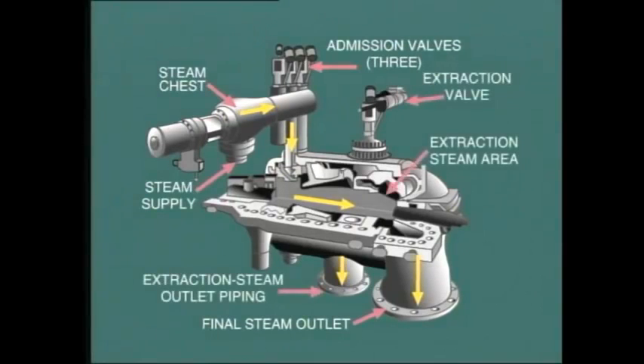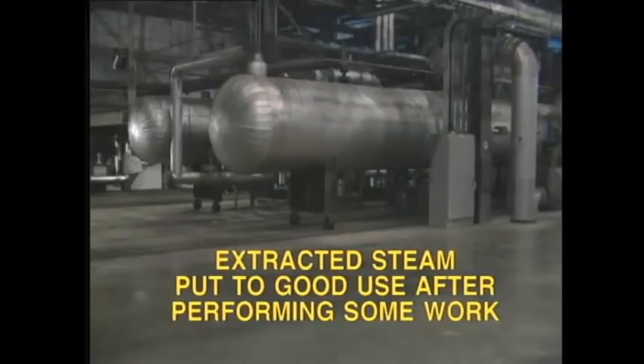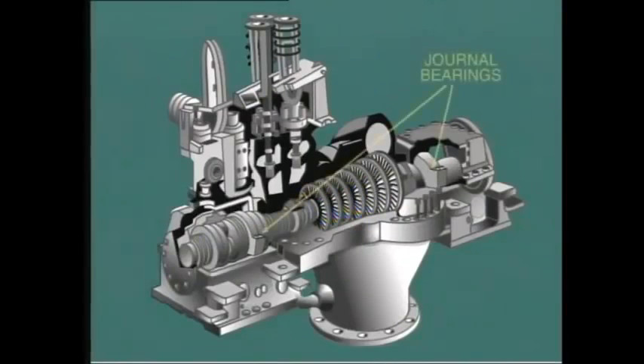At various stages along the steam path, steam is extracted from the turbine. This extraction steam is commonly used for feed water heating, but there may be other applications as well. The concept is that the extracted steam is put to good use after performing some work in the turbine. You will remember that we discussed this in the first tape in this series when we looked at efficiency. The turbine rotor is supported on journal bearings which are located at each end of the cylinder. It is essential that these bearings retain their correct alignment, as the clearances between the rotating parts and the fixed parts of the machine are extremely small.